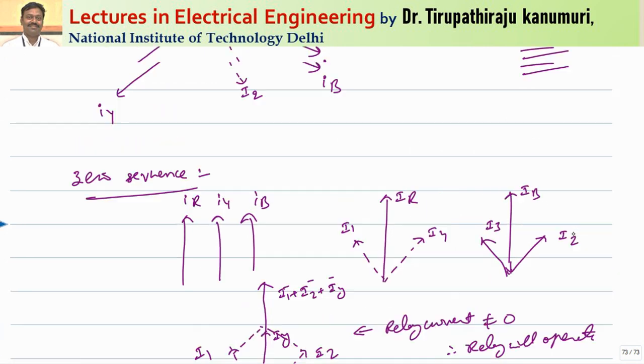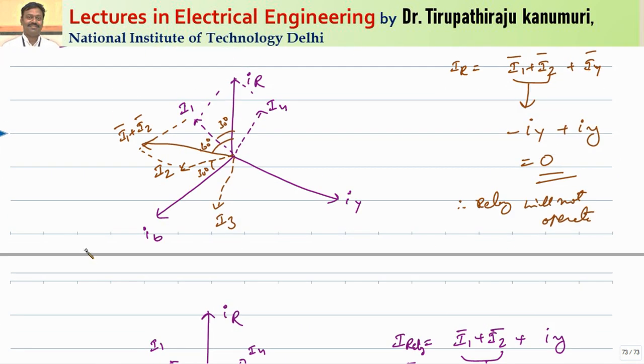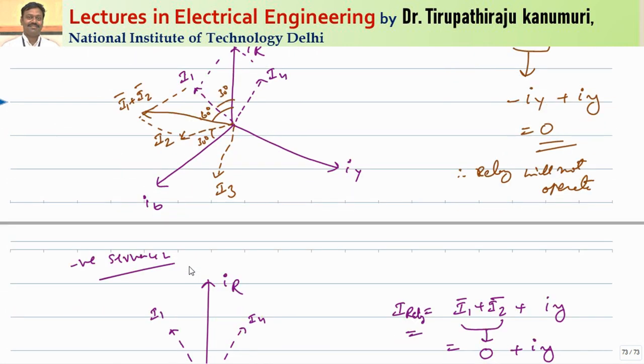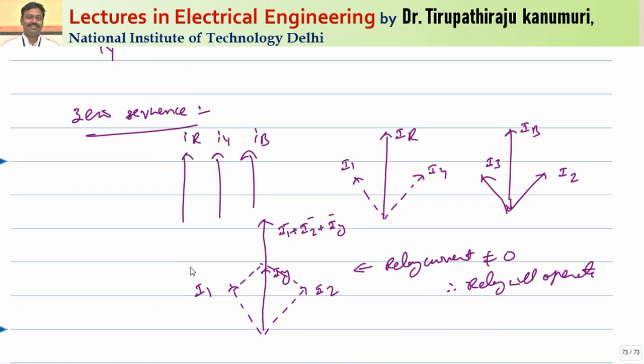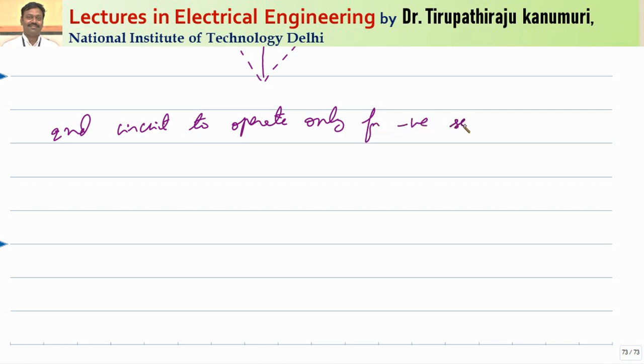We can observe from this that by using this bridge circuit, the relay senses both the negative sequence component and the zero sequence component, and will not operate for the positive sequence component. If you do not want your circuit to operate for the zero sequence component — only for negative sequence — there is a second circuit available.